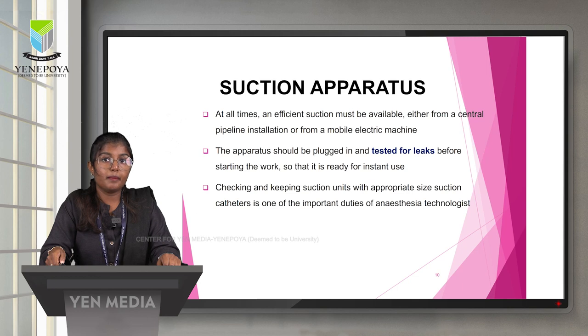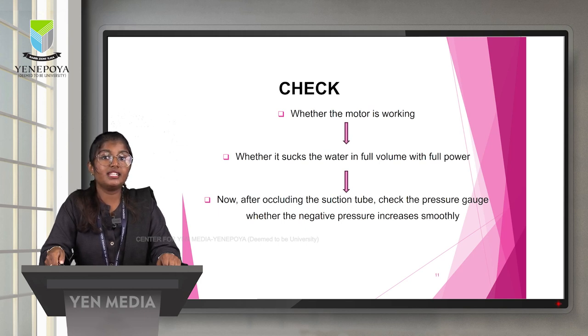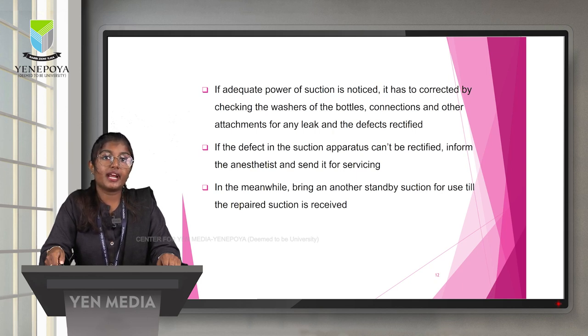Checking and keeping the suction unit with appropriate size suction catheters is one of the important duties of the Anesthesia Technologist. Check whether the motor is working and whether it suctions water at full volume and full power. After occluding the suction tube, check the pressure gauge to confirm that the negative pressure increases smoothly. If inadequate suction power is noticed, correct it by checking the washers of the bottles, connections, and other attachments for any leaks or defects.